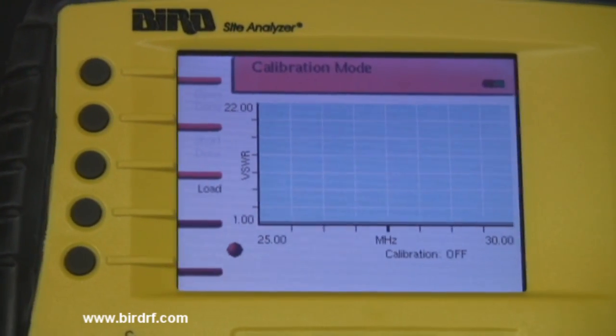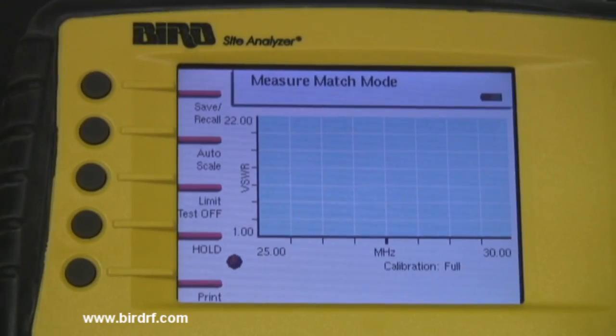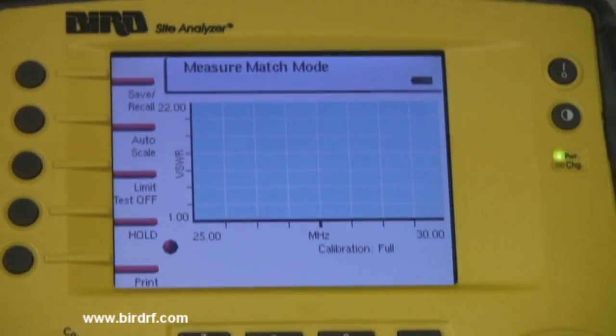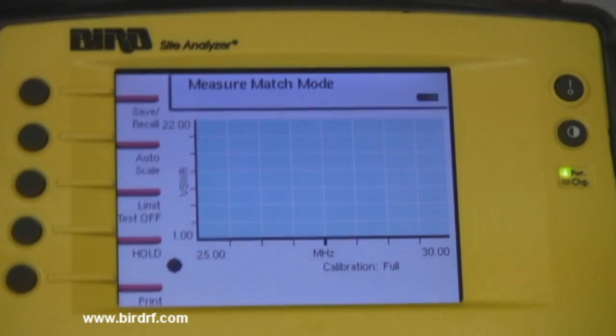Then press the load button and wait for the measure match mode to come up on the screen indicating that the calibration procedure has been performed. You have now completed the calibration process.